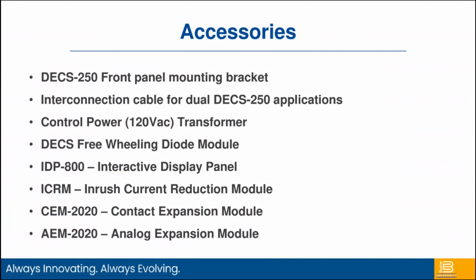And for certain applications, we may need some accessories. So the DECS, for instance, the DECS 250 is set up to be rear panel mounted, but we also have a front panel mounting bracket. Can do very similar things for other devices. We can add on interactive display modules or remote display panels, additional contact expansion modules or analog expansion modules, just to add more flexibility into the system itself.